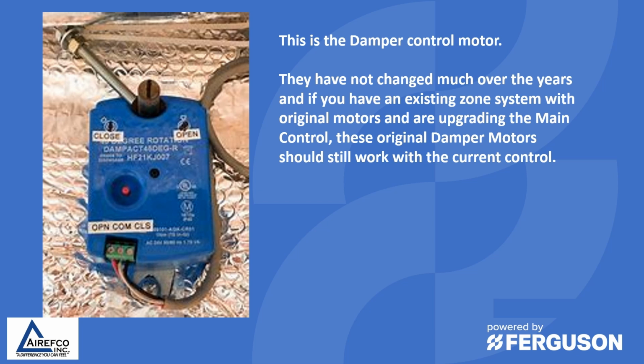This is the damper control motor. They have not changed much over the years, and if you have an existing zone system with original motors and are upgrading the main control, these original damper motors should still work with the current control.